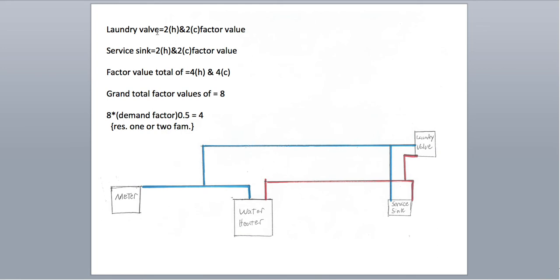So here we go. You have a laundry valve — factor value of two for the hot, two for the cold. And you also have your service sink — factor value of two for the hot, two for the cold. So your factor value totals are four hot, four cold. Your grand total factor values are eight. So you take eight, multiply it by the demand factor, which for residential one or two family is 0.5. Eight times 0.5 gives you four.